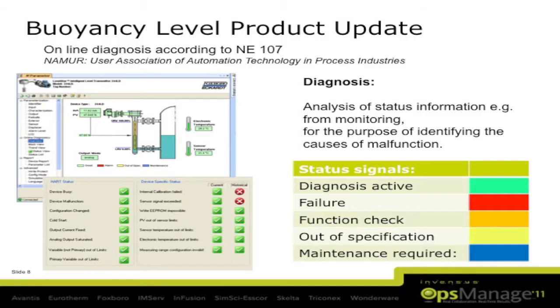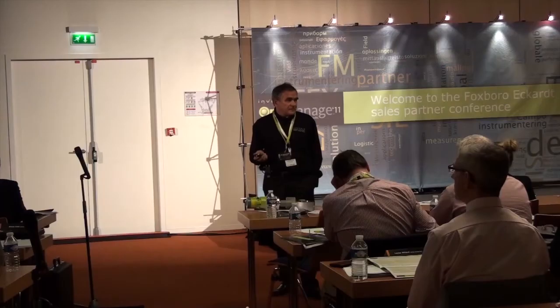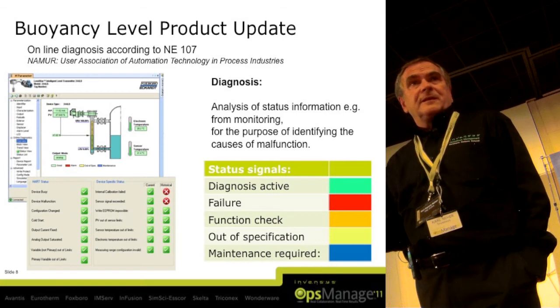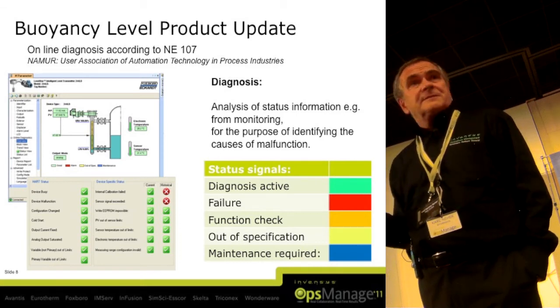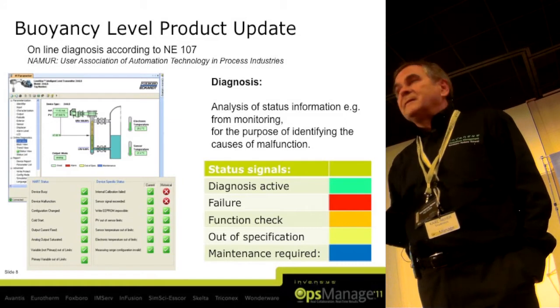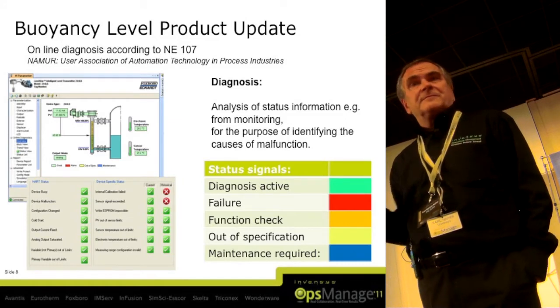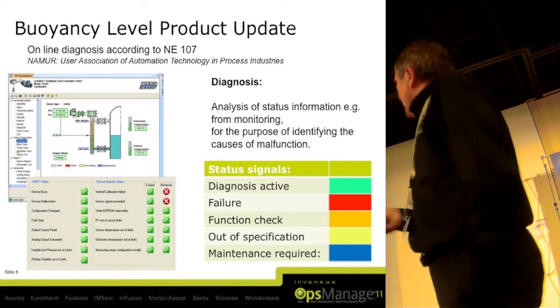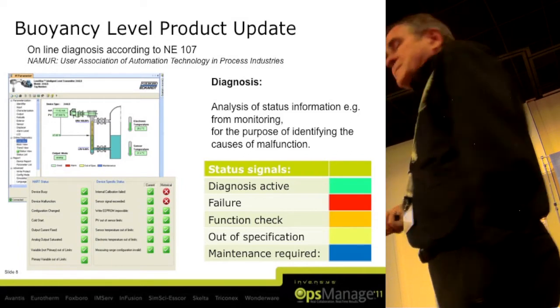The NE107 document consists of about 30 pages. Important is that diagnostic is an analysis of the status information from monitoring for the purpose of identifying the cause of malfunctions. Ideally, I have to know my transmitter will fail in 6 weeks. This is the ideal situation. We have some features built in on the positioners, that they can analyze a trend. We do not have this yet on the buoyancy level transmitter. This will be next. But at the moment, we have a number of status signals.